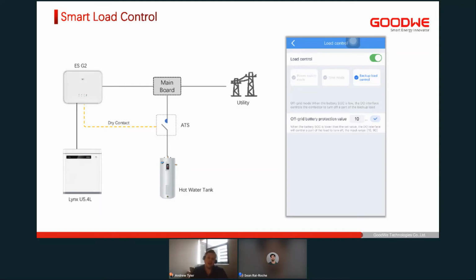So via software integration, you'll see on the right of this slide, there's a screenshot of our app. You've got a load control section, and you can choose different ways, either doing it via timing. So you could say, at 5 o'clock every day, switch it on, at 6 o'clock, switch it off. And you could also do backup load control too, such as setting when you would like the load to switch on or off based on a battery state of charge level. And the way this works is we've got a dry contact in the inverter, which is depicted by the yellow dashed line, and from there it will essentially send a signal to an ATS or an auto transfer switch that will switch either on or off based on what we've specifically set.